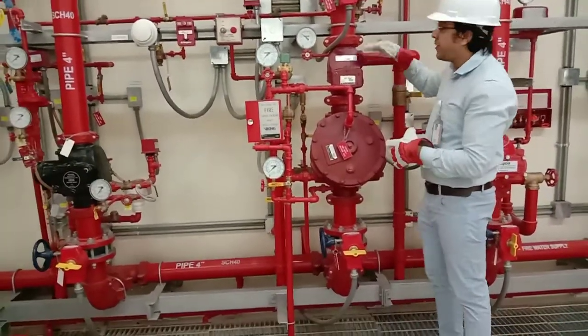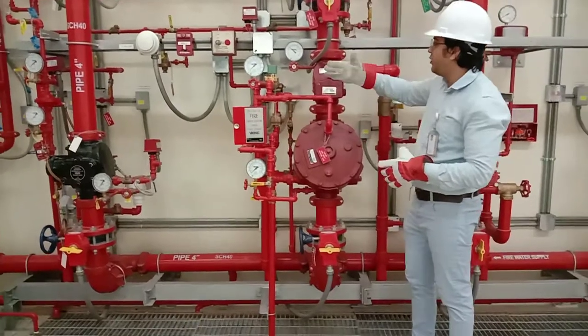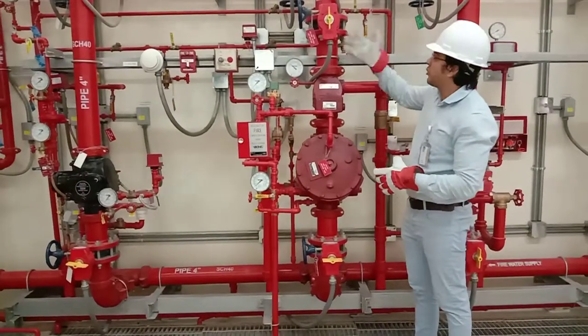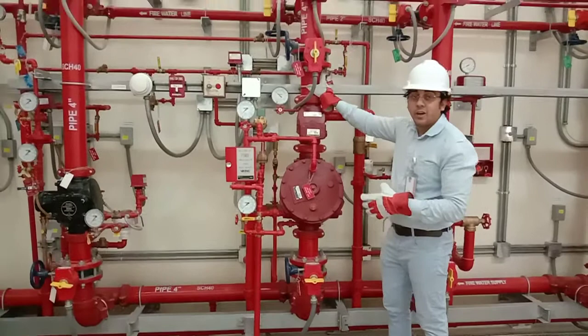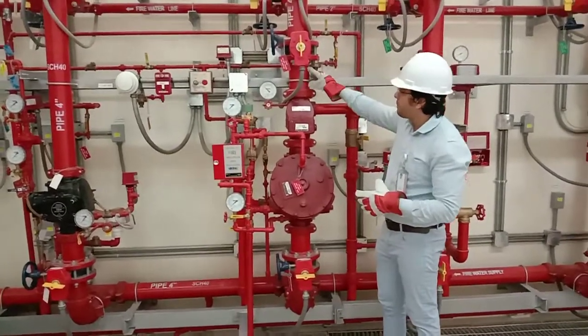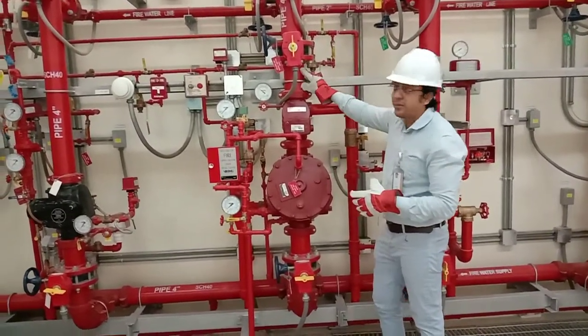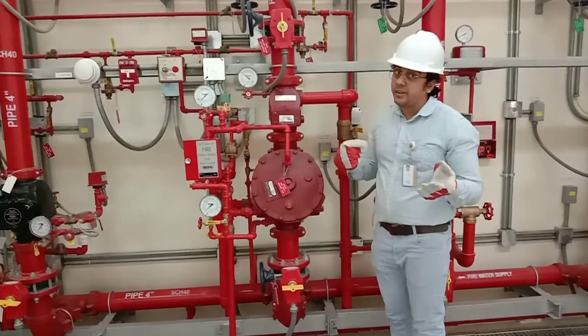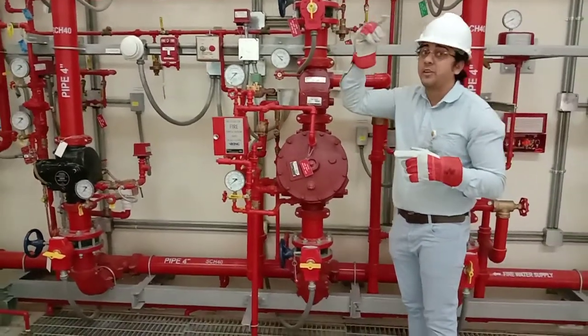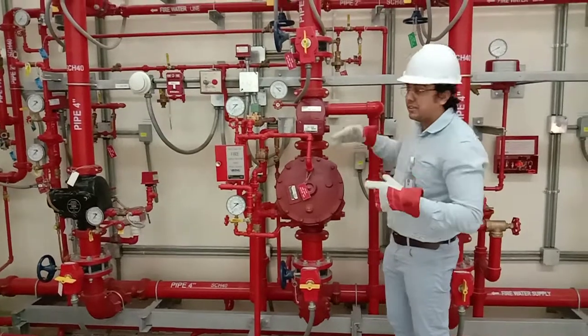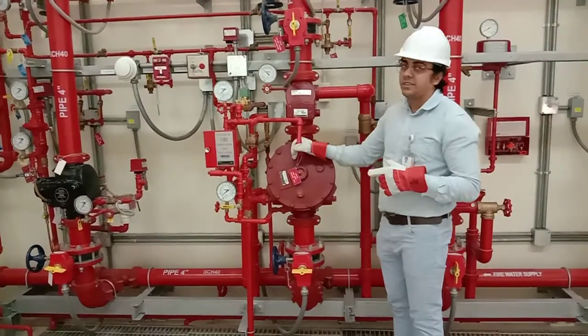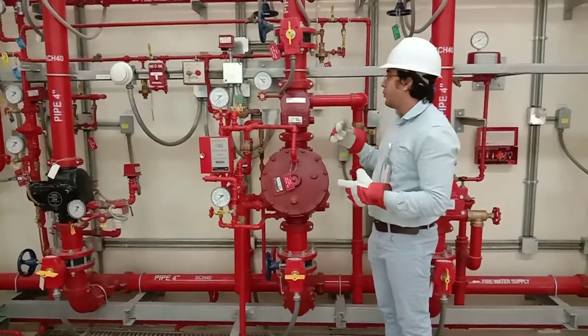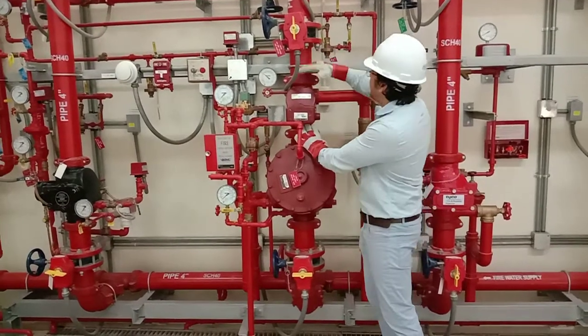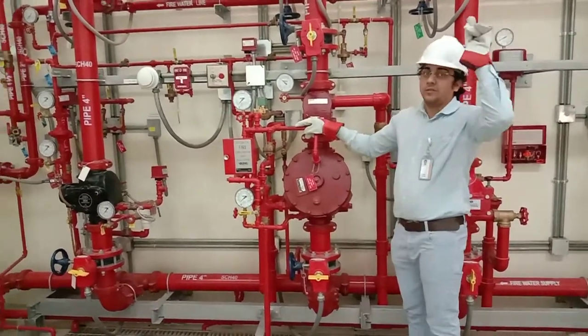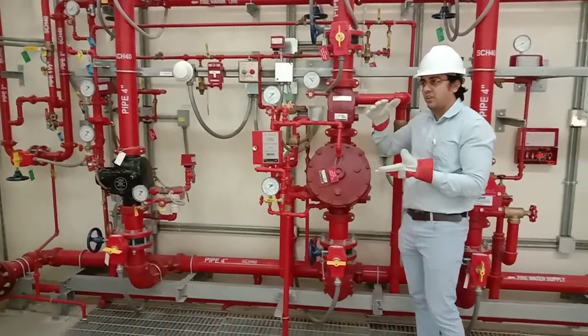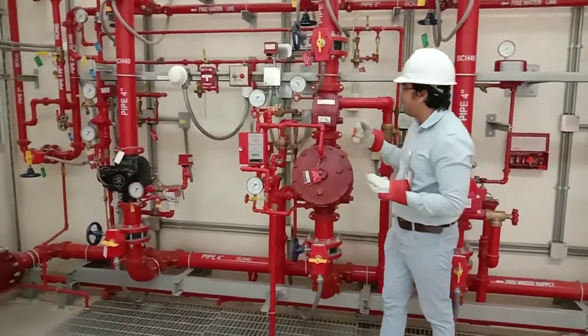But at the same time, we have a check valve, right? This check valve will only open like this, but from the top side, we have air pressure. So that air pressure will only reduce when there is an actual fire and when the sprinkler system is fused. So in any case, after this one, it will again come to the reset position and normal position. So for the water going after this one, we need to fuse the sprinkler system, right? So that the pressure difference of the air will go and the system will be activated.